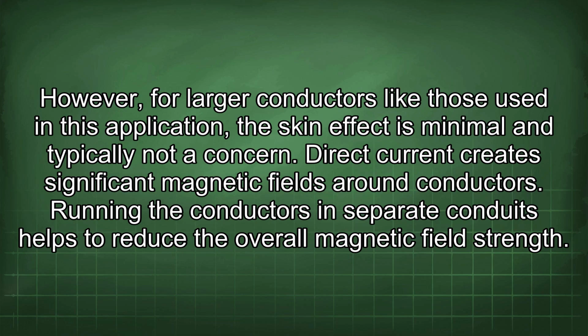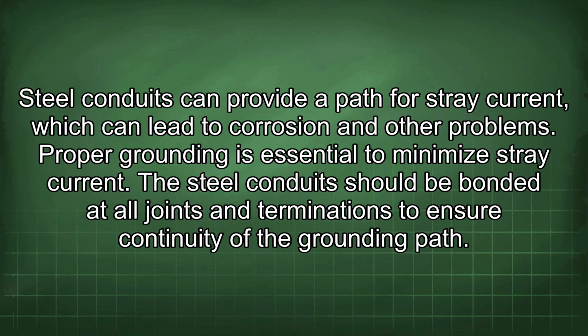Direct current creates significant magnetic fields around conductors. Running the conductors in separate conduits helps to reduce the overall magnetic field strength. Steel conduits can provide a path for stray current, which can lead to corrosion and other problems.